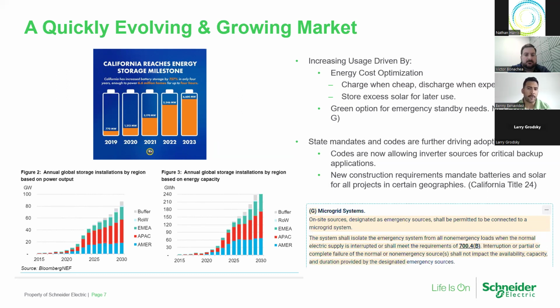Also driven by code, as you mentioned, it's referenced in the National Electric Code, Article 700.12(G), where you can utilize microgrid systems as an emergency standby source. And battery energy storage systems have several use cases. They can do frequency regulation, help with peak demand. They're also a valuable backup power source. They do have a finite duration, but if you design them properly, you could utilize that energy storage system for a resiliency application.